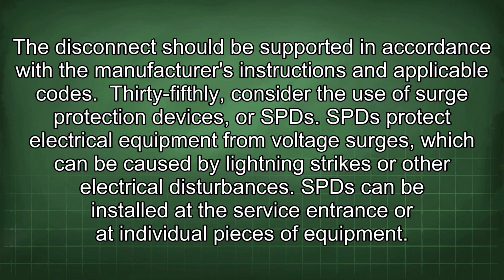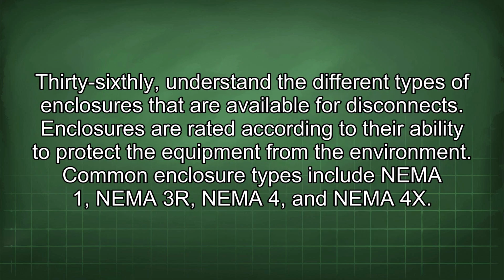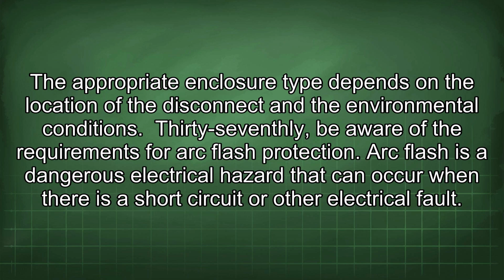35th, consider the use of surge protection devices, or SPDs. SPDs protect electrical equipment from voltage surges, which can be caused by lightning strikes or other electrical disturbances. SPDs can be installed at the service entrance or at individual pieces of equipment. 36th, understand the different types of enclosures that are available for disconnects. Enclosures are rated according to their ability to protect the equipment from the environment. Common enclosure types include NEMA 1, NEMA 3R, NEMA 4, and NEMA 4X. The appropriate enclosure type depends on the location of the disconnect and the environmental conditions.